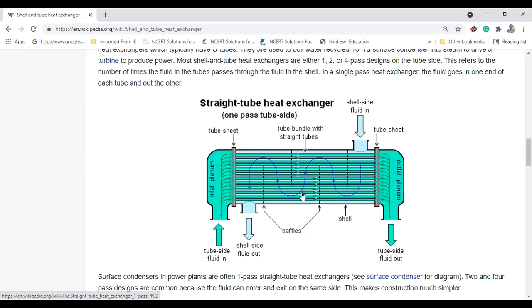If a tube is damaged, you stop the operation, remove that tube, and insert a new one. If the shell is damaged, the entire mechanism goes wrong and you have to reconstruct the work. When dealing with corrosive fluid — such as highly concentrated alkalis or acids — keep it on the tube side, because replacement of tubes is easier than replacement of the shell. You can select specific steel or higher alloy steel tubes to prevent corrosion.